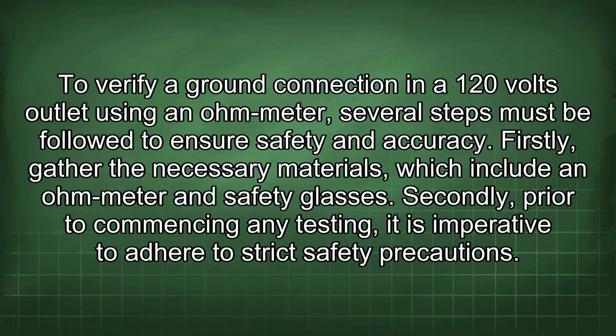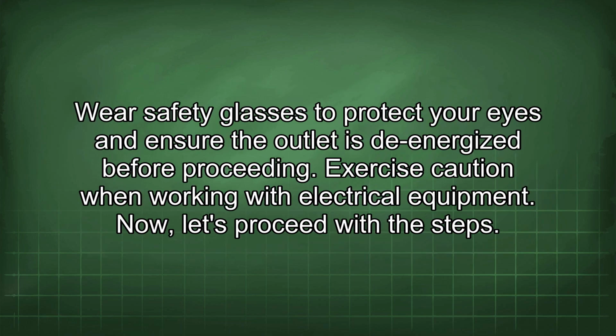To verify a ground connection in a 120 volts outlet using an Ohm-Meter, several steps must be followed to ensure safety and accuracy. Firstly, gather the necessary materials, which include an Ohm-Meter and safety glasses. Secondly, prior to commencing any testing, it is imperative to adhere to strict safety precautions. Wear safety glasses to protect your eyes and ensure the outlet is de-energized before proceeding.